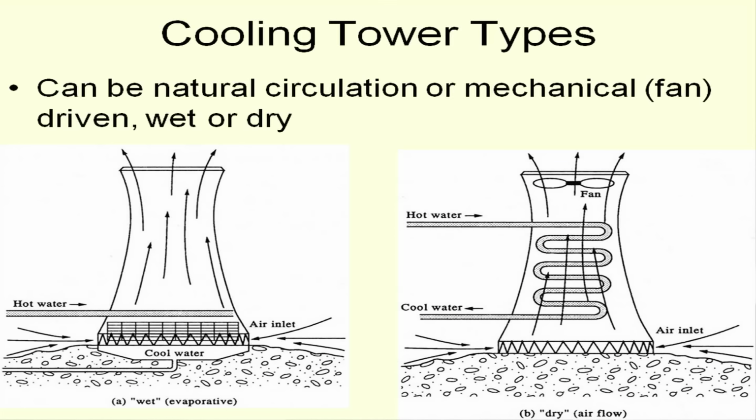Let me talk a little bit about some of these cooling towers. This shows two cooling tower concepts. On the left is the so-called wet or evaporative tower, where the hot water comes in and gets sprayed and has direct contact with the air. Evaporative cooling is the way that works, and your cool water comes out. And this tower design is natural circulation.